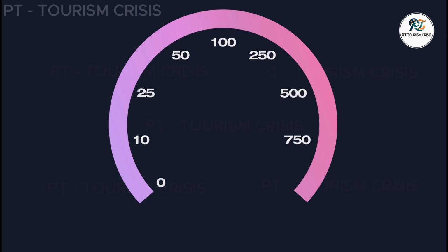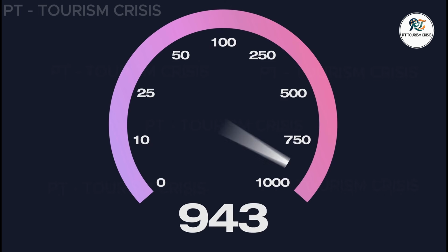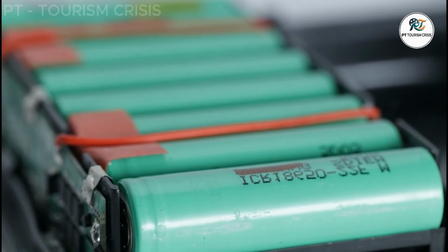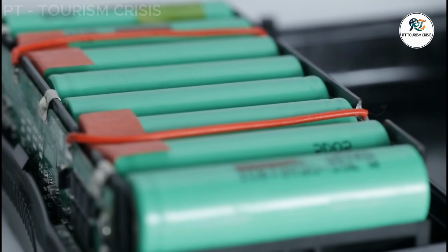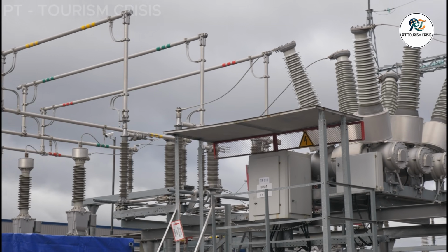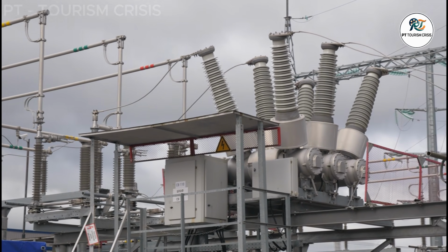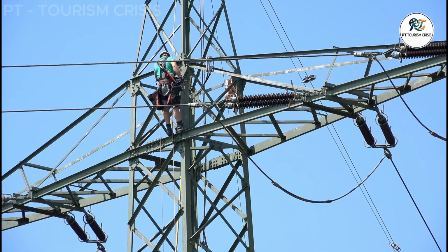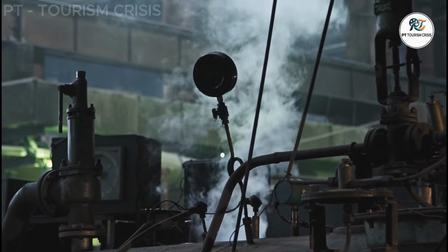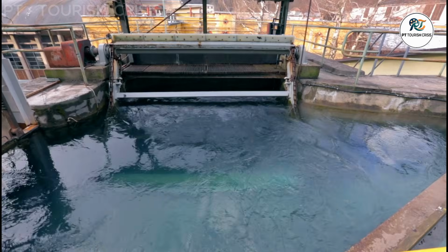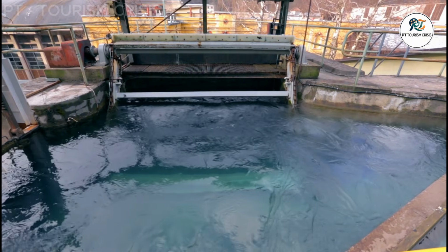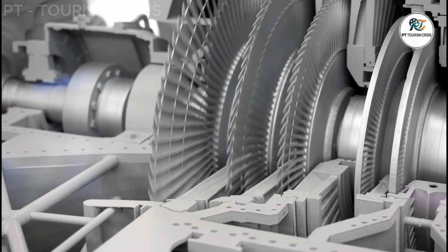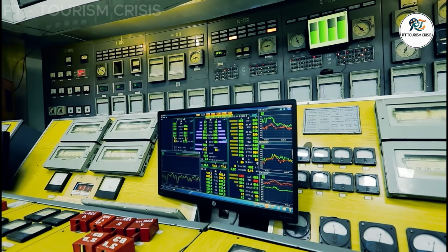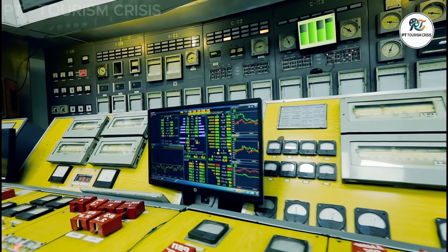When we run the speed test, the chemical battery wins almost immediately. Utility-scale lithium batteries are incredibly powerful for short-term grid flexibility. They work by converting electrical energy into stored chemical potential. When the grid demands power, the discharging phase simply reverses that chemical process. There is no massive mechanical steam cycle required to start up, no physical reservoir of water that has to build momentum before it can turn a heavy turbine. The electrical output can be controlled electronically in fractions of a single second.